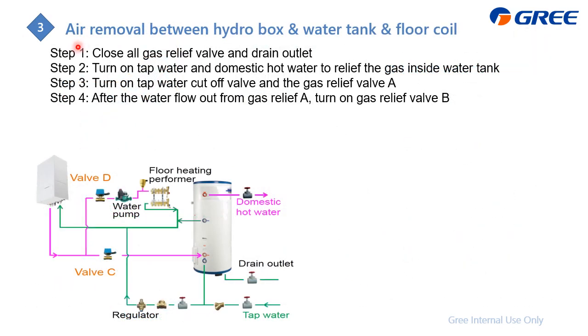Next is to remove the air between the hydro box, the water tank, and the floor coil. Here I just listed the steps for the most complicated system, the DHW water tank plus the floor coil. First is to close all the gas valves and also drain the water out. Then step 2 is to turn on this tap water, which conducts the water here, and also open this one. The purpose is just to release all the air inside this DHW water tank.